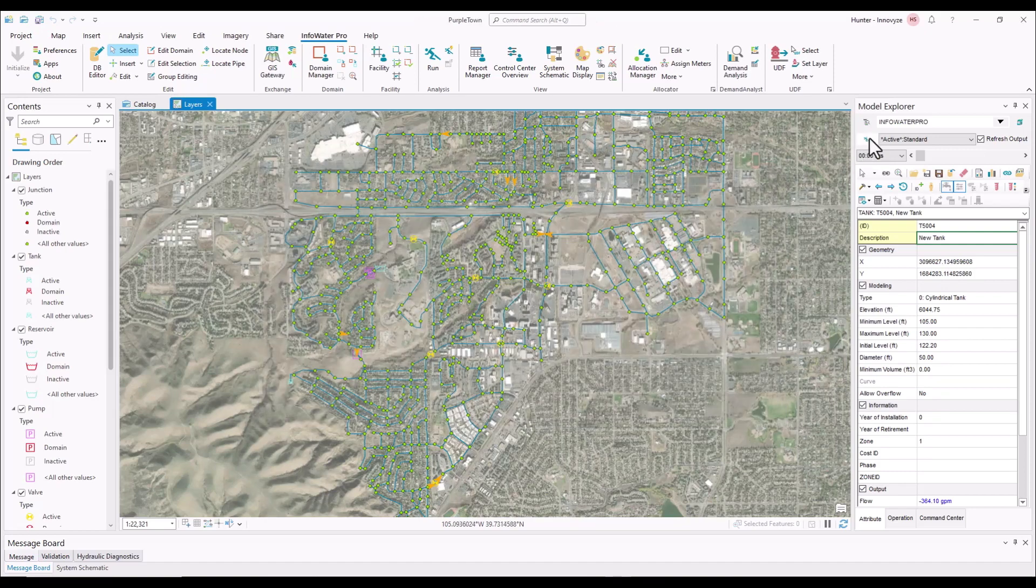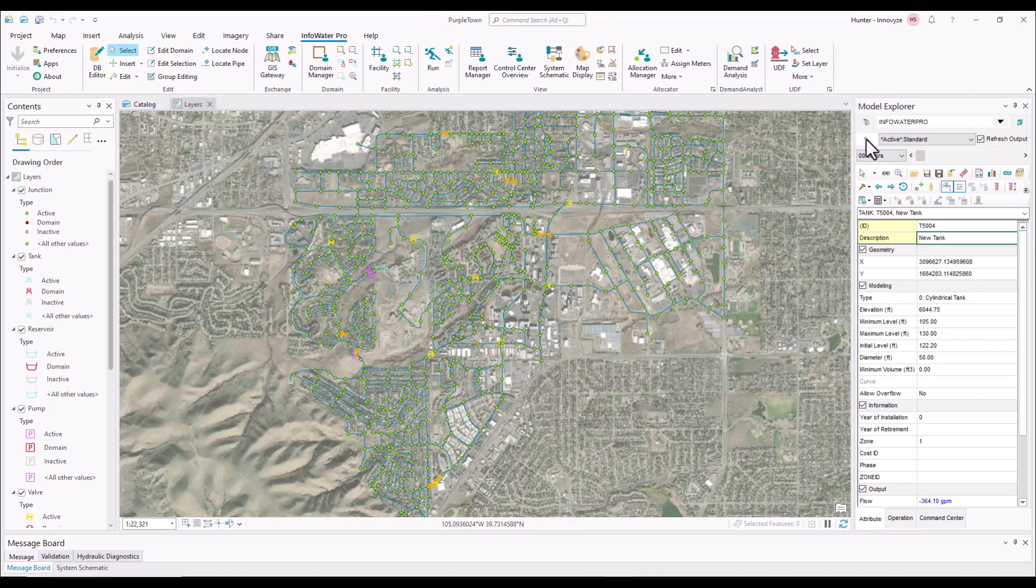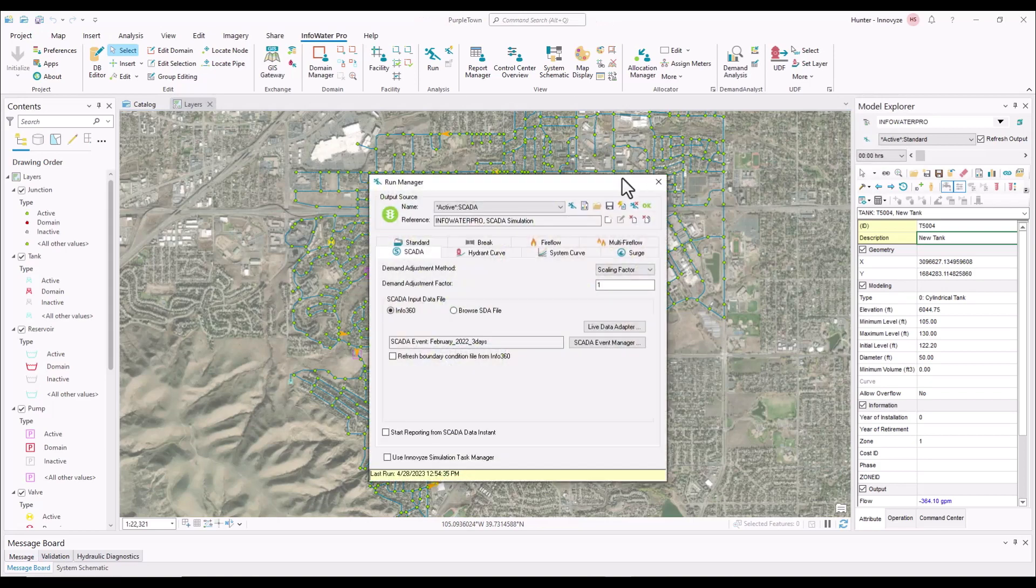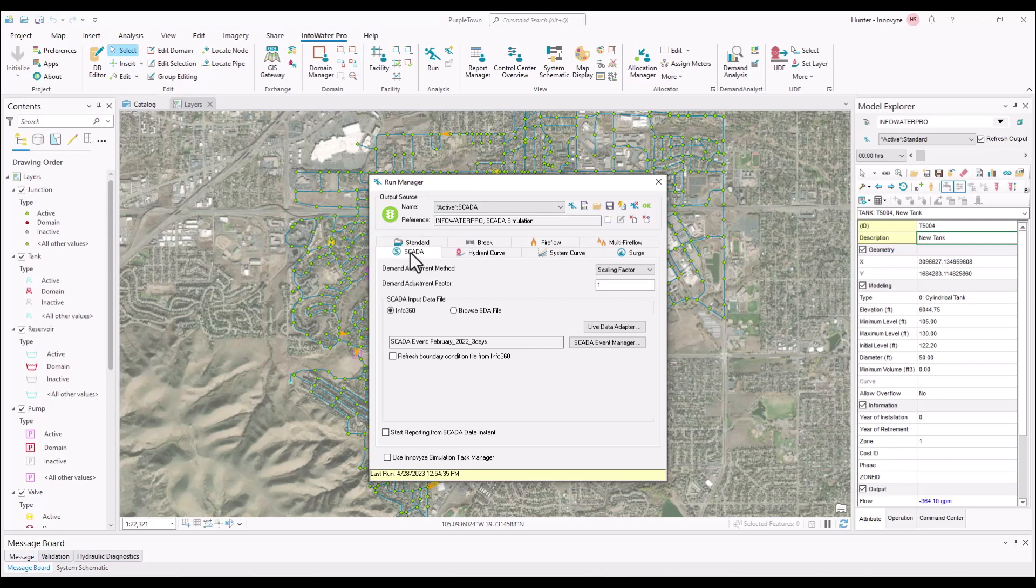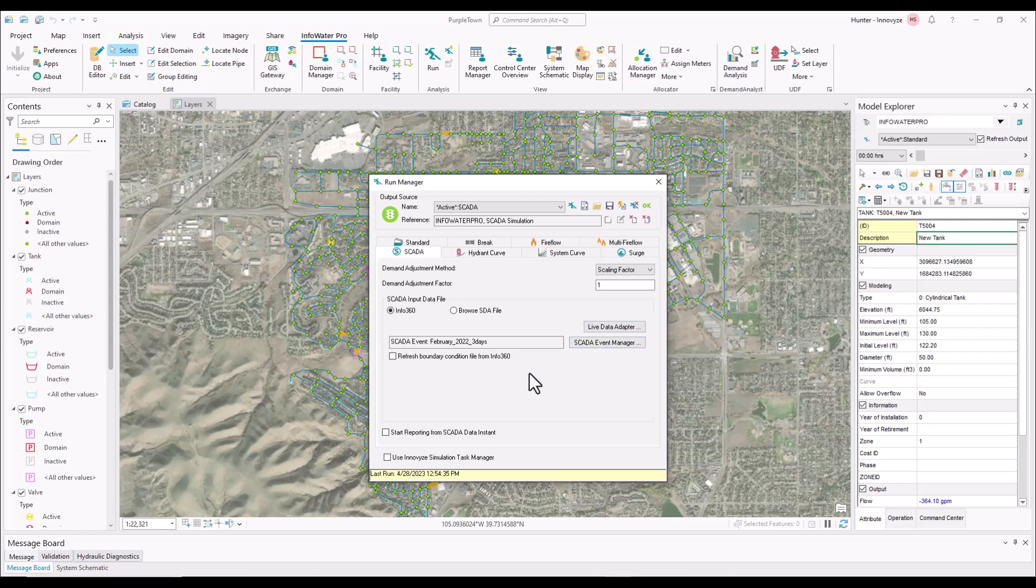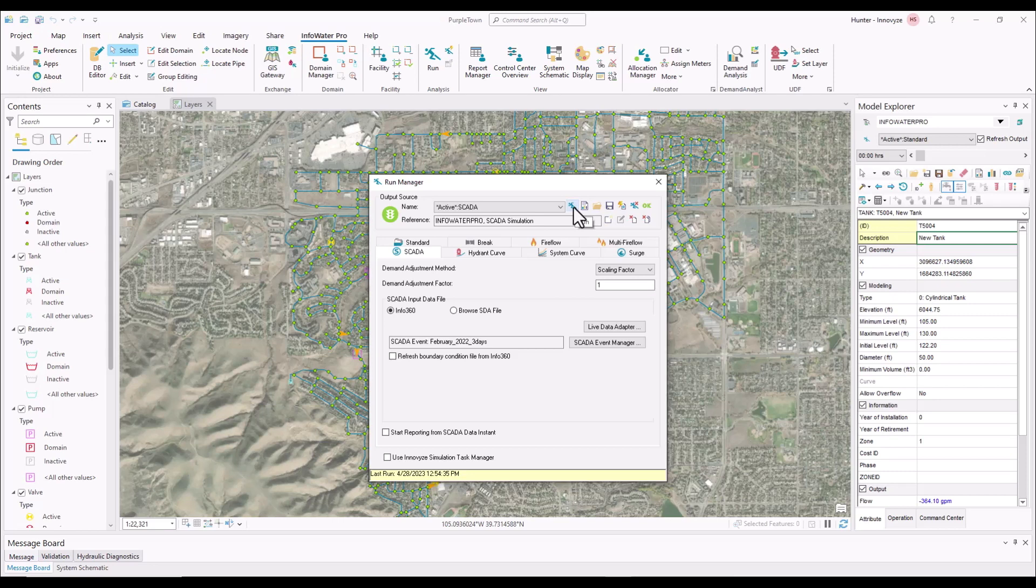Next, we're going to go to the Run Manager under the Model Explorer, and make sure you start by going to the SCADA event. There are some changes you can do here with demand adjustments, choosing if you want to pull the information from Info360 or an SDA file. You could also come to the Live Data Adapter directly from the screen or create a new SCADA event, refresh the boundary conditions, and some other options within this Run Manager. But since we're just going to keep it normal using the February 2022 three-day that we already established, we can go ahead and press Run.